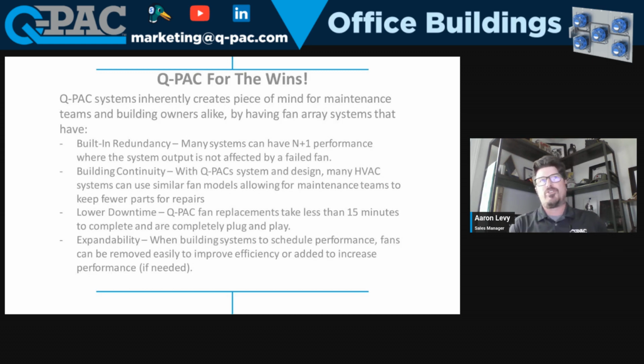And this is something that we talk about with Q-PAC, the way it was designed and the way it's engineered is that we have that built-in redundancy. If a fan does fail, the rest of the fans in the system will spool up to compensate for that lost fan. It takes about 10 or 15 minutes to change out a fan. So they're never really down for very long.